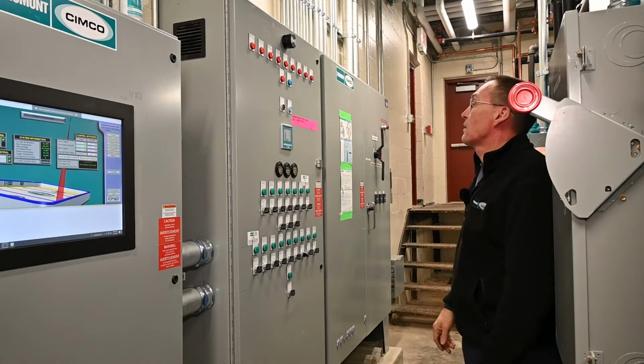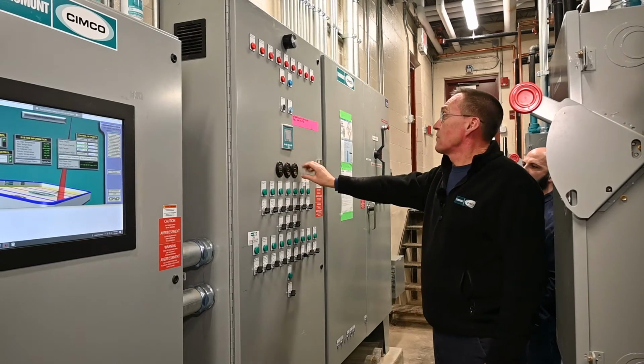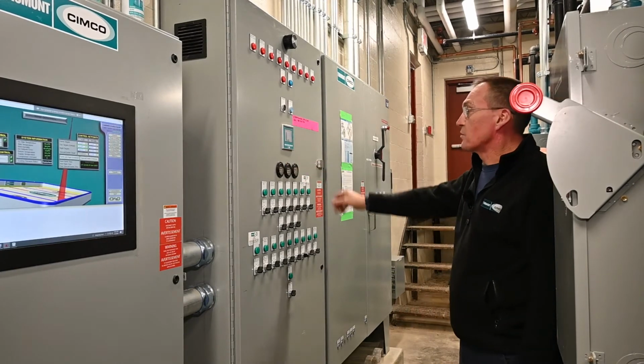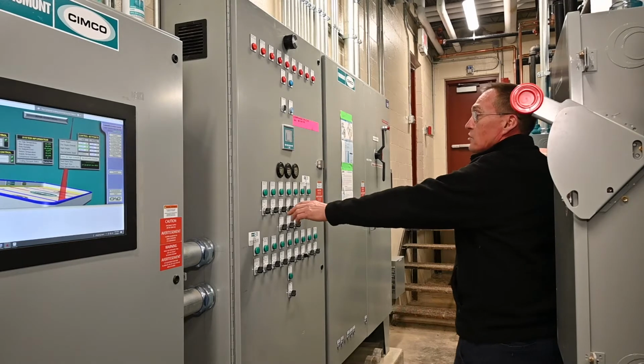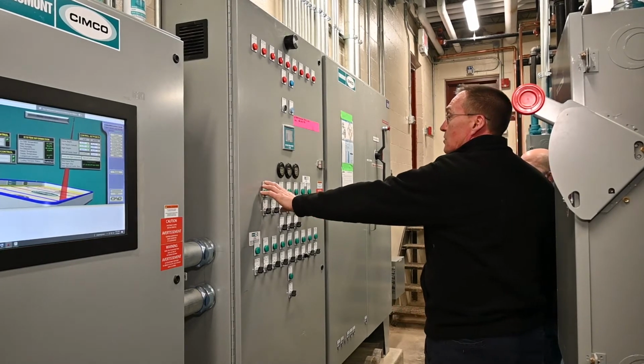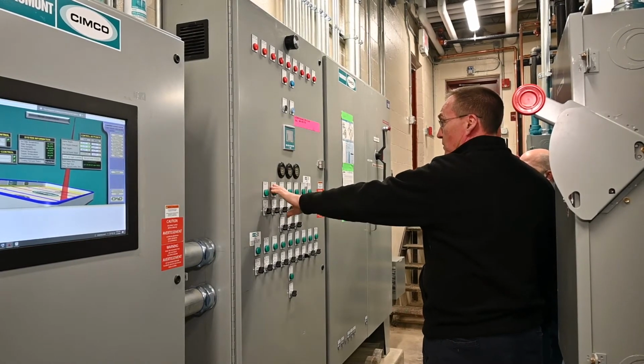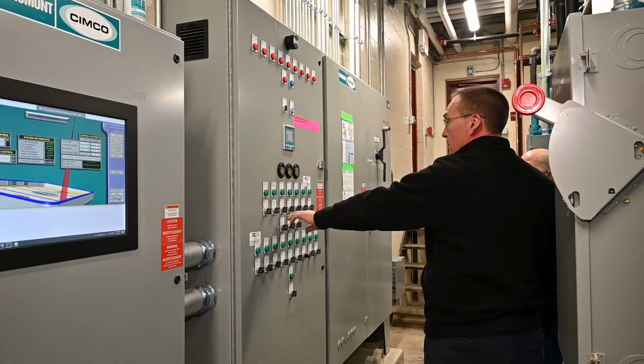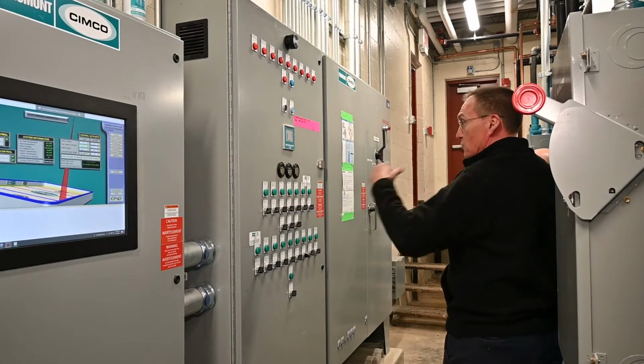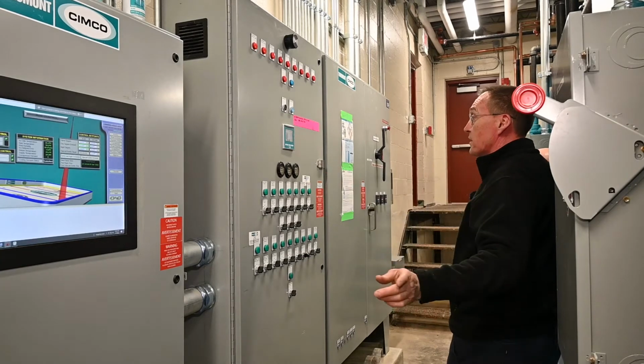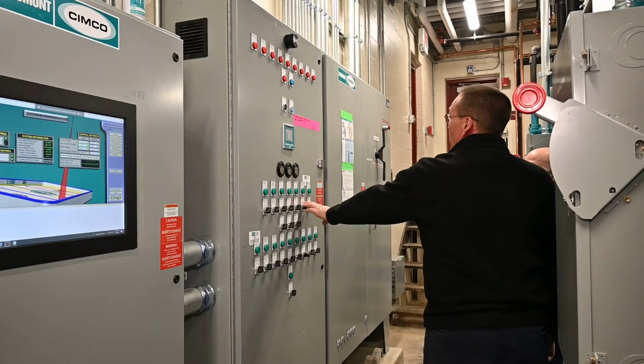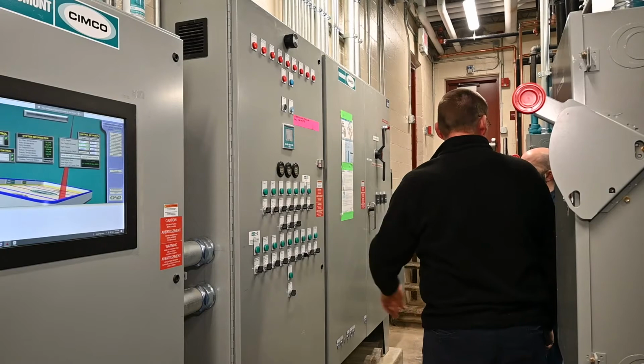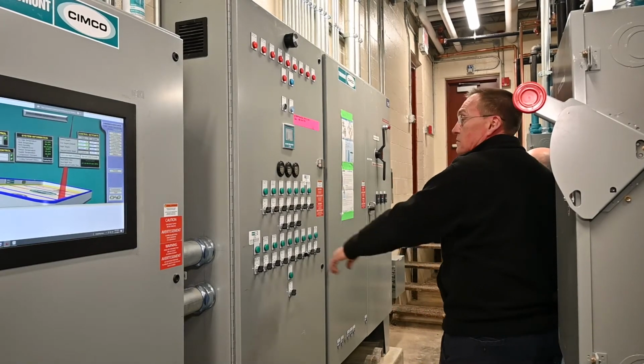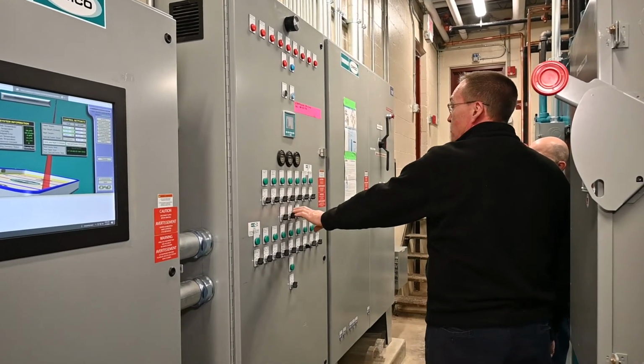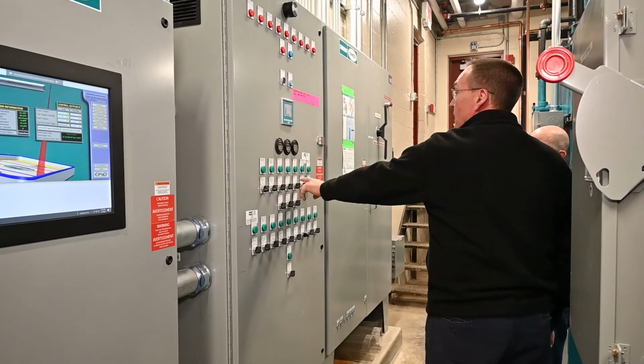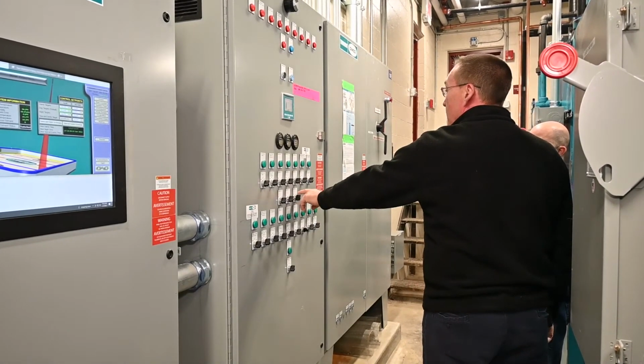Okay? You have hour meters for compressor 1, 2, and 3. Hand-off-auto switches for cold pump 1, which is your cold floor pump number 1 over there. P2, again over there. Compressor 1 behind your back, 2 behind my back, and compressor 3 over there. Pump P3 and P4 are your warm loop pumps. Those are the ones over there against the wall. Compressor 1, 2, and 3. As you see, these have hand and auto, and then you have on and off.